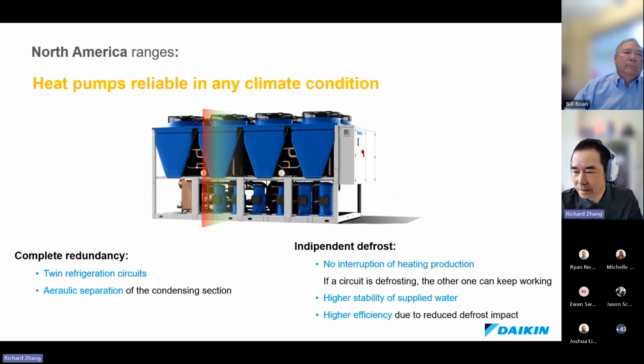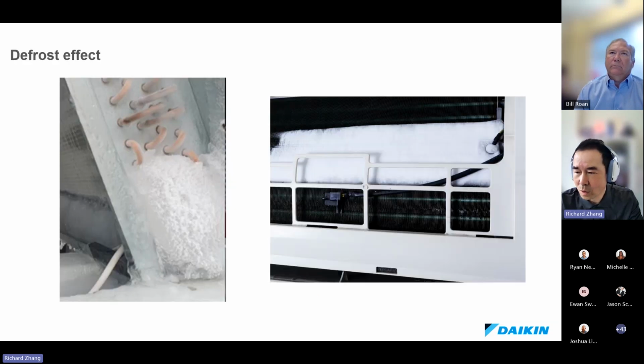We basically divided the unit into two separate refrigerant circuits, and then they run independently. On the one hand, they provide redundancy to each other from a capacity point of view, but from a defrost control point of view, it can be a huge advantage. So one circuit is in defrost, the other one is still providing the hot water into the hydronic loop.